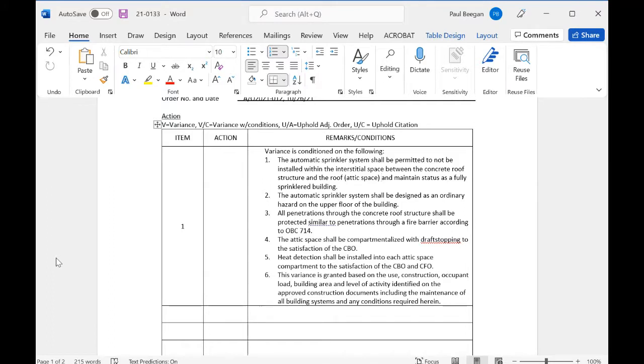The variance is conditioned on the following. Number one, the automatic sprinkler system shall be permitted to not be installed within the interstitial space between the concrete roof structure and the roof parapet attic space, and shall maintain status as a fully sprinklered building. Number two, the automatic sprinkler system shall be designed as an ordinary hazard on the upper floor of the building. Number three, all penetrations through the concrete roof structure shall be protected similar to penetrations through a fire barrier according to Ohio Building Code Section 714.